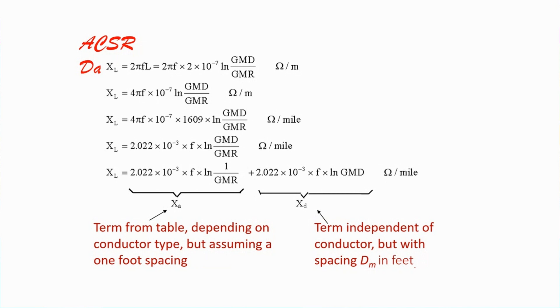So, the geometrical mean radius, GMR, is dependent on the conductor itself and its strands. For the manufacturer to present this in the data sheet, we do a simple thing: we take L multiplied by omega to get XL total, then split it into two parts. One part has the common constant factor and 1 over GMR, the other part is GMD. GMD is decided by the designer, based on the situation. XA, the first part, is dependent on the conductor, so this is what we calculated for XA, the part dependent on the conductor itself.